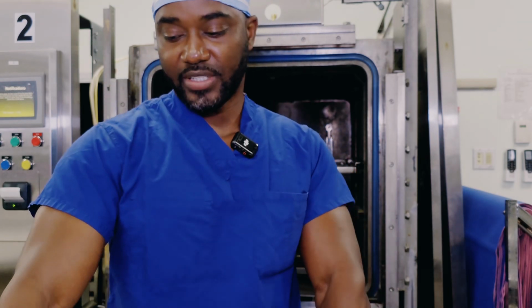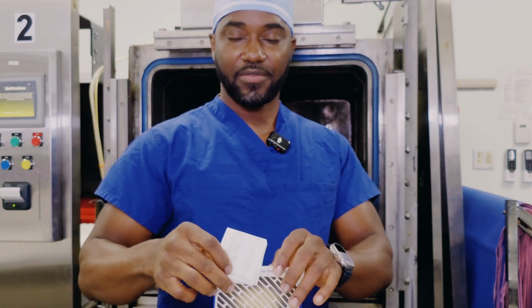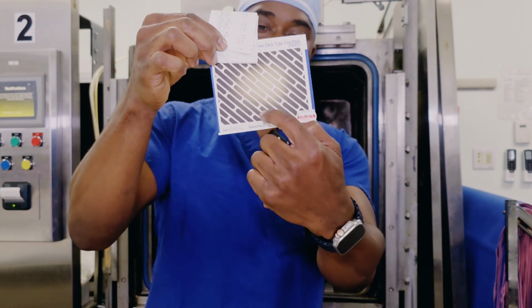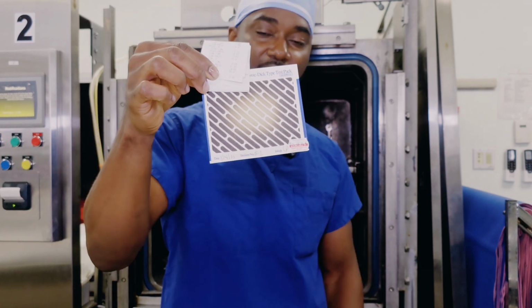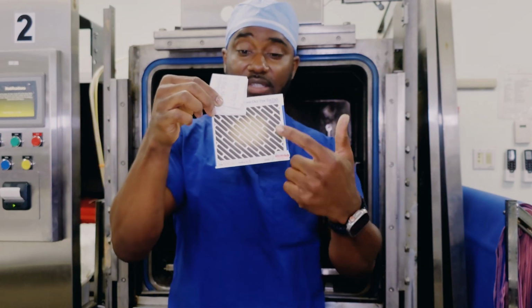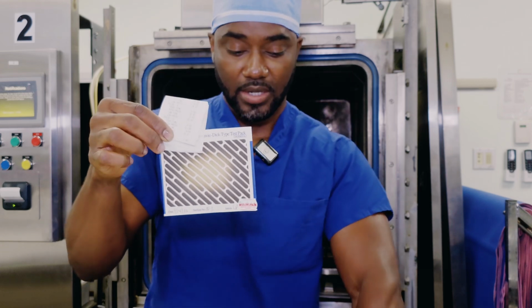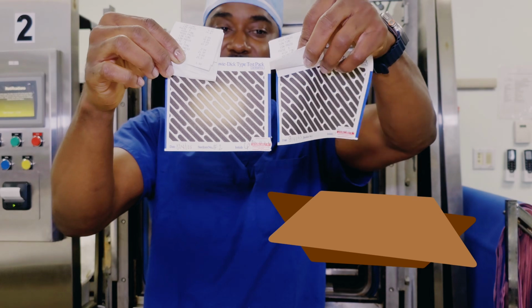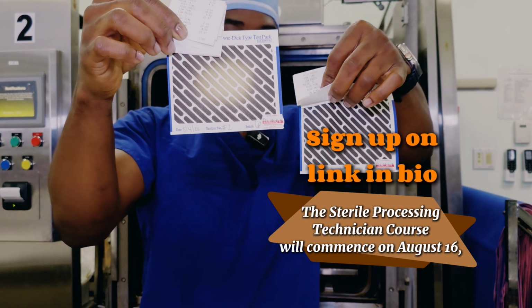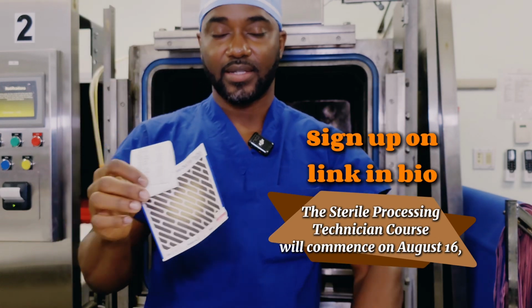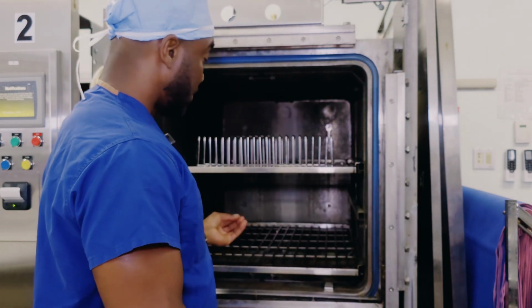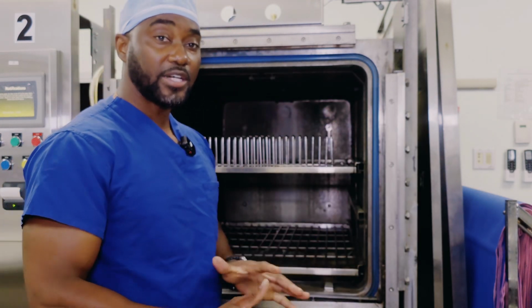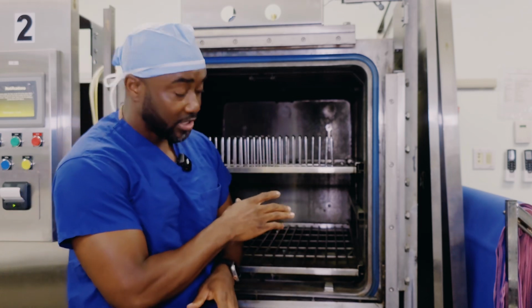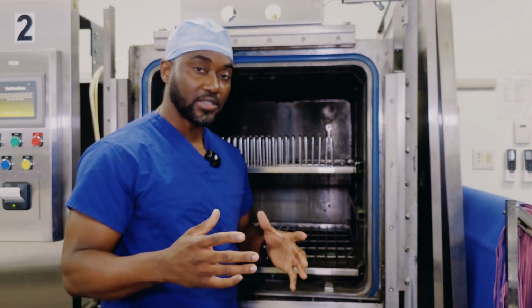A failed Bowie-Dick test result, however, will give you a little gray area in the middle of the packet. So this result has failed. This is a failed Bowie-Dick test result. Putting them side by side, you see what a Bowie-Dick test that has passed looks like compared to one that has failed. If you have this failure, it shows that air is not adequately pulled from this chamber, thereby leaving air within the chamber. It means you cannot sterilize the load for that day.